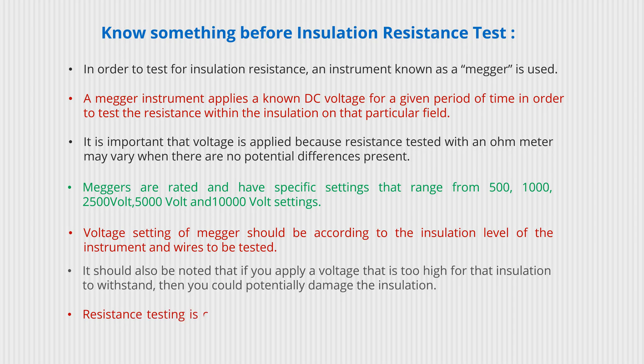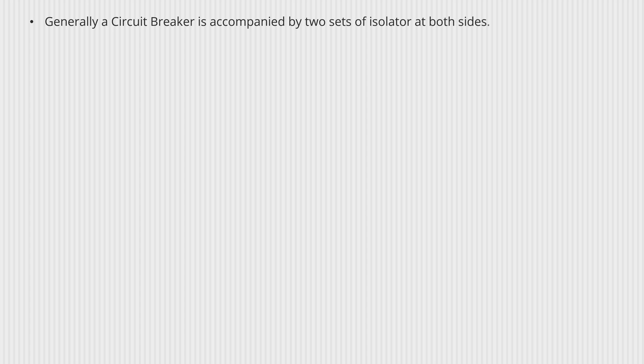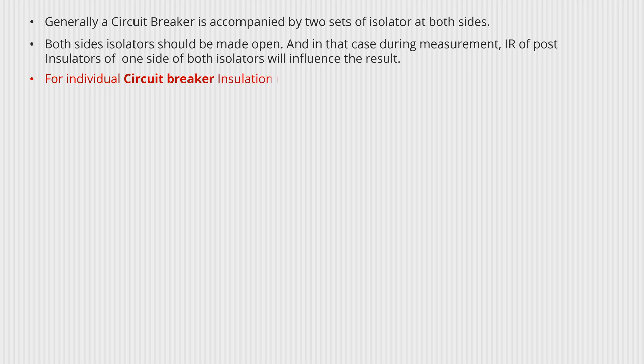Insulation resistance testing is crucial for verifying that the insulating materials which make up the breakers are performing correctly. Generally a circuit breaker is accompanied by two sets of isolators on both sides. Both side isolators should be made open, and in that case during measurement, the IR of post insulators of one side of both isolators will influence the result for individual circuit breaker insulation resistance testing.